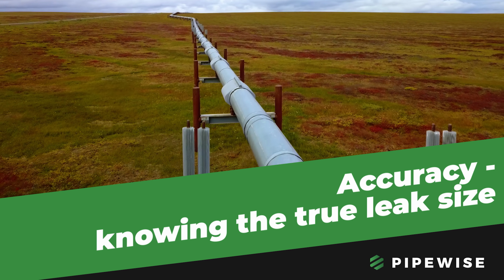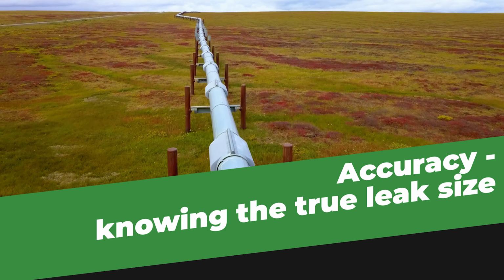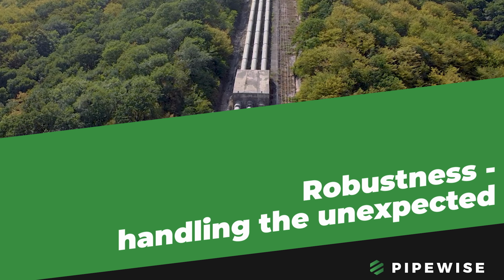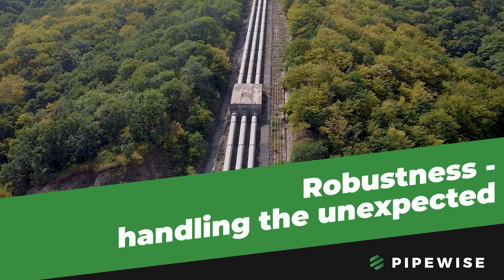When we talk about accuracy of a leak detection system, really what we mean is, is this going to be able to find leaks? If there's a 1% leak, if there's a 2% leak, is the system going to be able to pick up on that? Every system is going to have a threshold. For example, probably won't be able to find a 0.1% leak on a pipeline, but as that leak gets a little bit bigger, as maybe the pinhole starts to expand a little bit, you want to be catching that as soon as possible. The second one that I would talk about is going to be robustness.